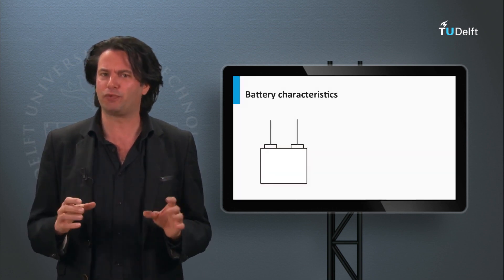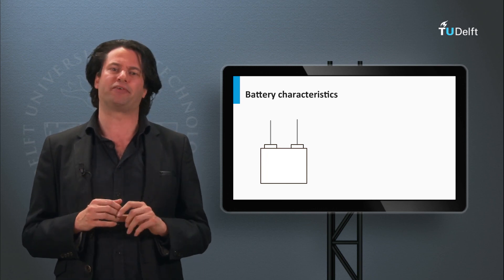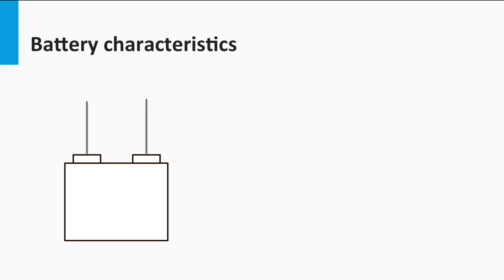I will first start with the voltage and capacity ratings of the battery. Every battery is rated with a certain voltage and capacity. The battery rated voltage is the nominal voltage at which the battery is supposed to operate. The so-called solar batteries or lead-acid grid plate batteries are usually rated at 12 volts, 24 volts, or 48 volts. Of course, the battery system in your PV system can attain any voltage based on the interconnection of several batteries at the system level.